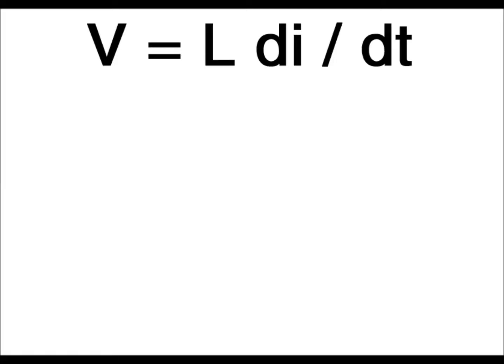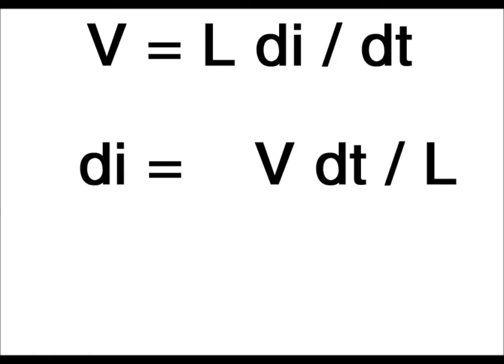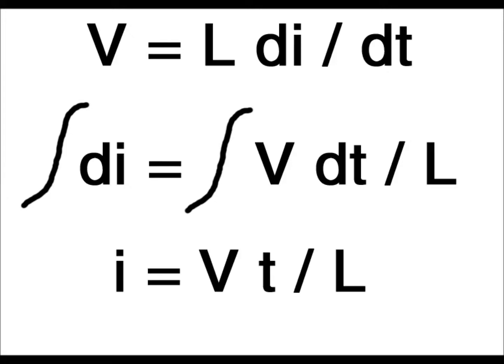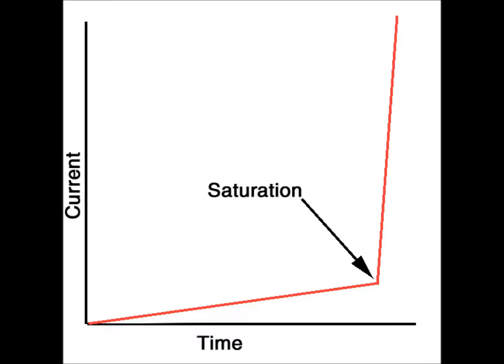I'm going to perform a little bit of calculus on this, but don't worry, I won't overwhelm you. First, we rearrange the equation, getting dI on one side of the equation and all the other variables on the other side. Then we take the integral of both sides of the equation. The integral of dI is simply I, and the integral of V dt divided by L is the voltage times time divided by the inductance. Since both the voltage and inductance are constant until the iron core saturates, this means that the current is going to gradually increase with time until it reaches the point of saturation. Once saturation is reached, we use the same equation. However, now the inductance is a much smaller value, which means the current will increase at a much faster rate.